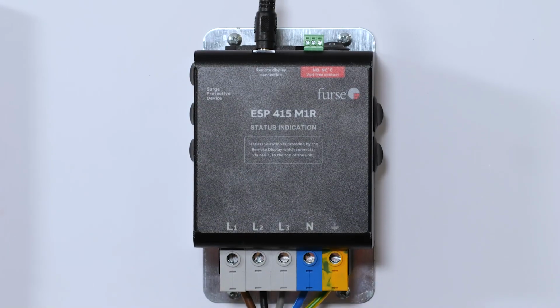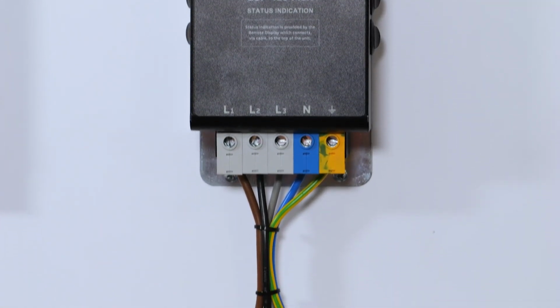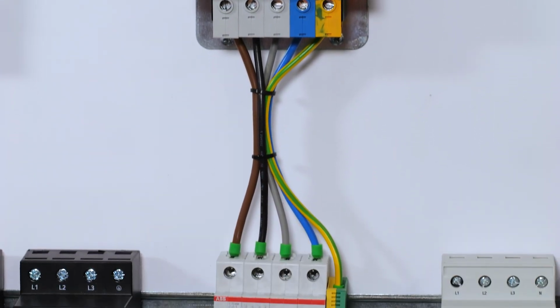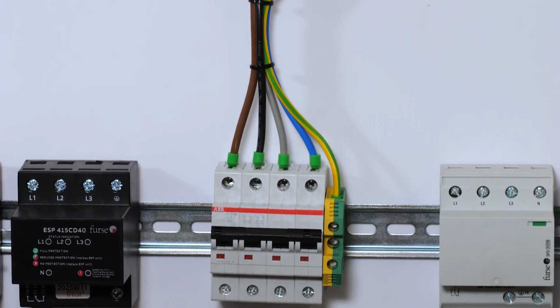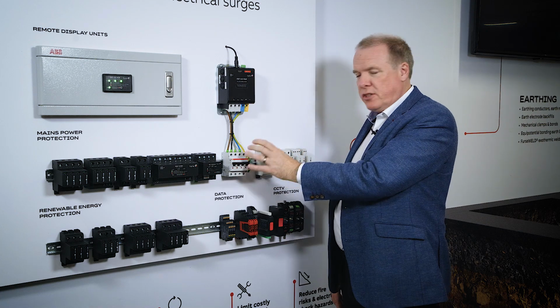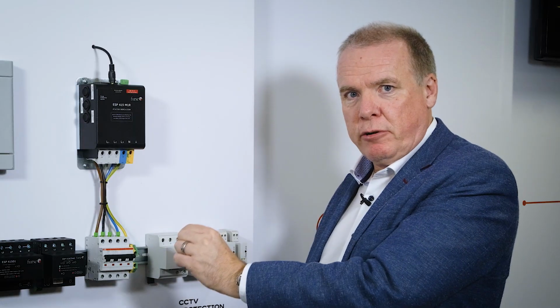And you can see it's installed close to the main switch. Now the golden rule with SPDs is you always install them as close as possible to the main switch or the main service intake. That is absolutely critical.